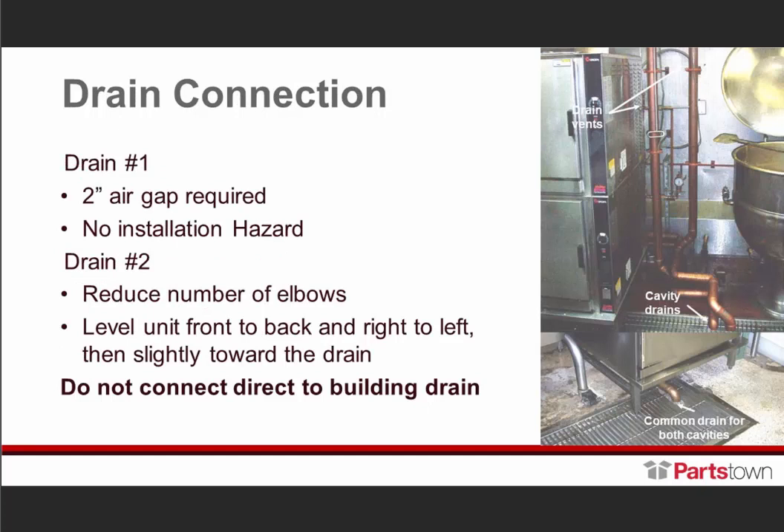Now, the drain connections. Drain one — there is a two-inch air gap required. No installation hazards. For drain two, reduce the number of elbows. Level the unit front to back and right to left, slightly towards the drain. Here you're seeing the drains and the number of elbows — I'll be honest, I visited this site and didn't know if they were getting paid by the elbow.